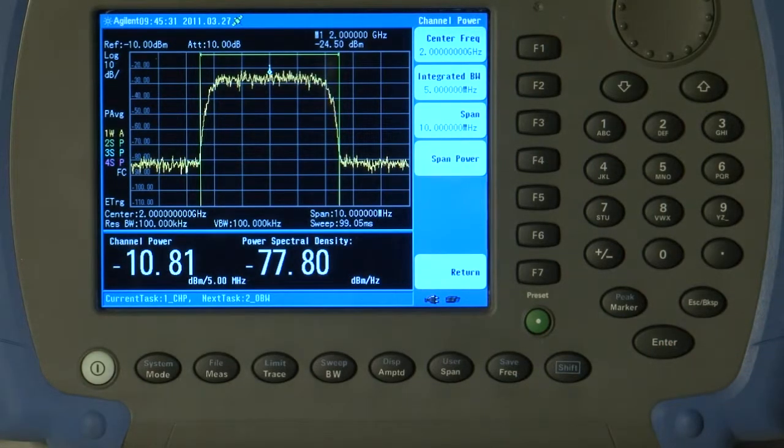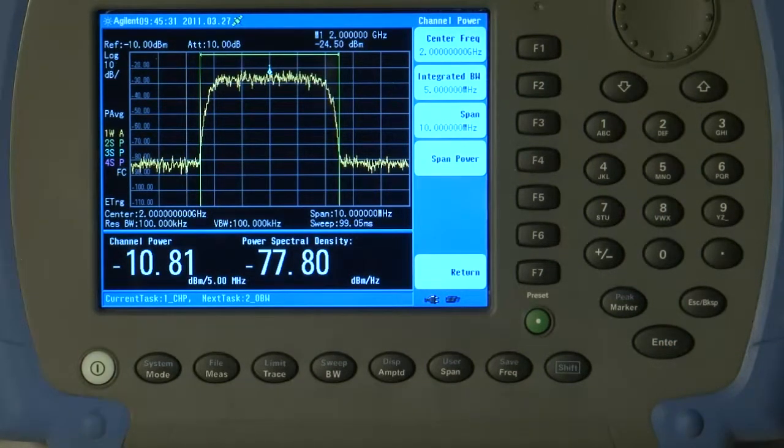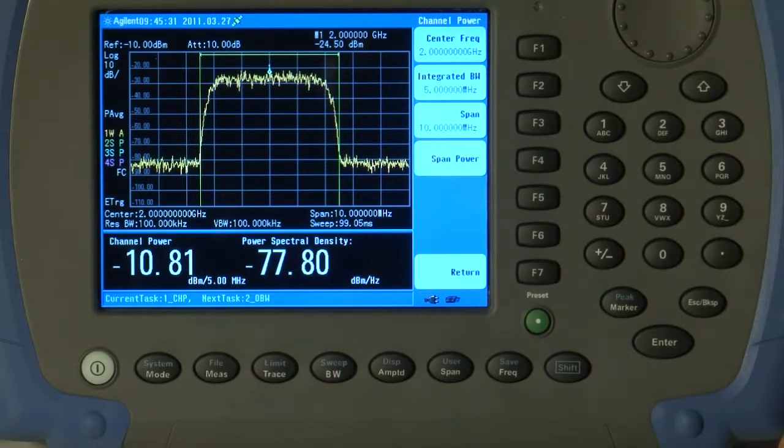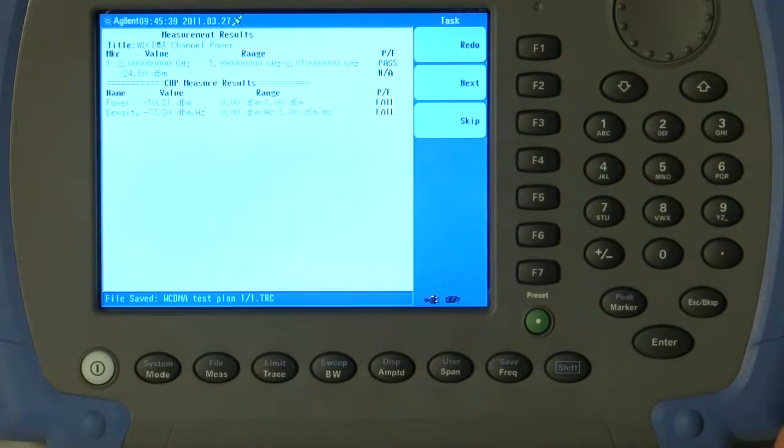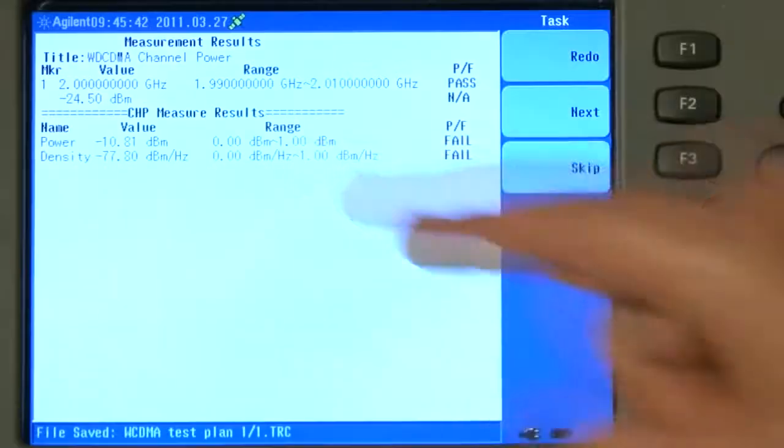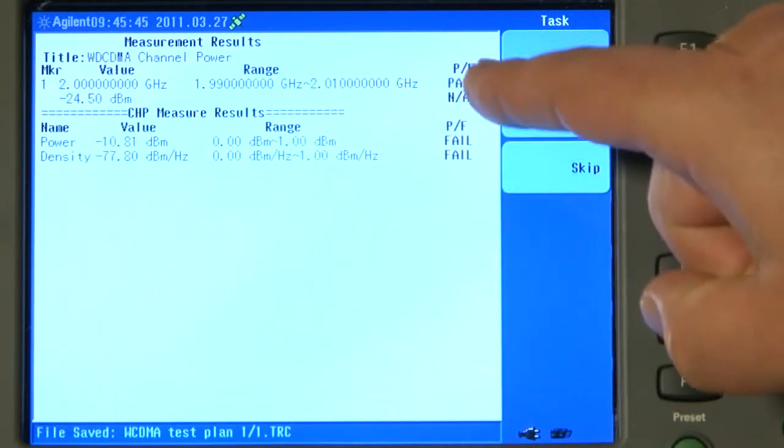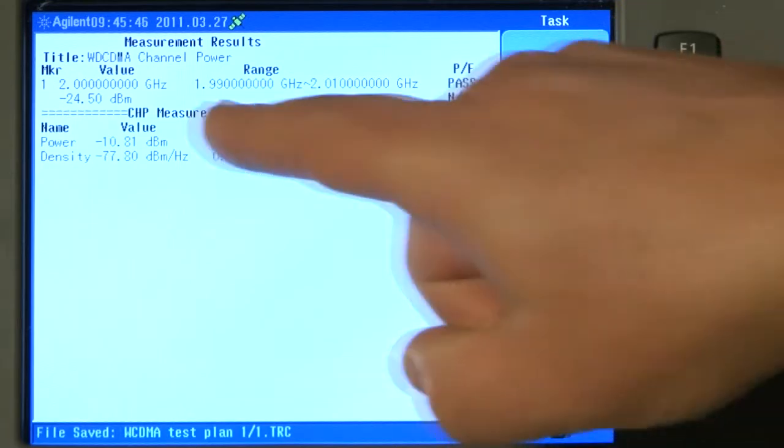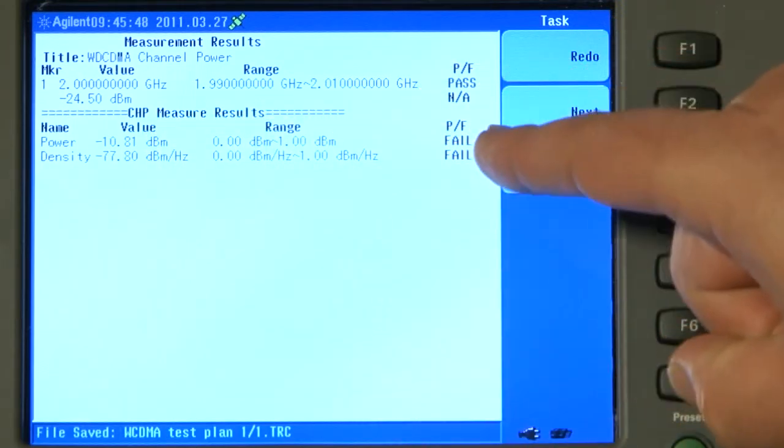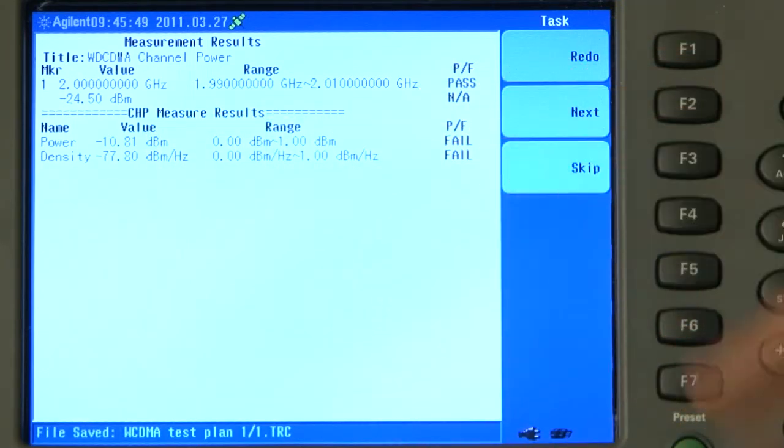The instrument is now making the first measurement, which is WCDMA Channel Power. It is saving the screenshots and creating a text file with the test results. Here you can see the measurements it is making of the marker value, whether it pass or fail, and here are the channel power measurement results again, indicating pass or fail.